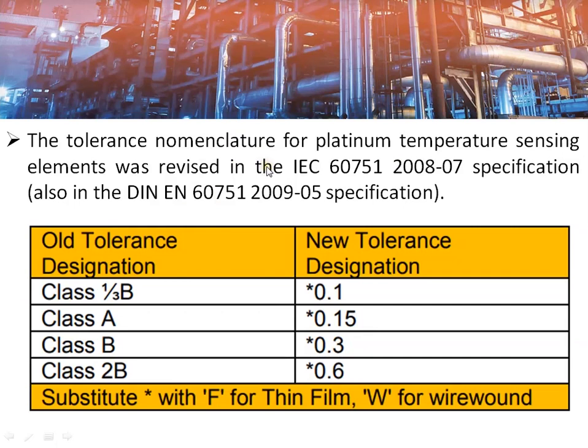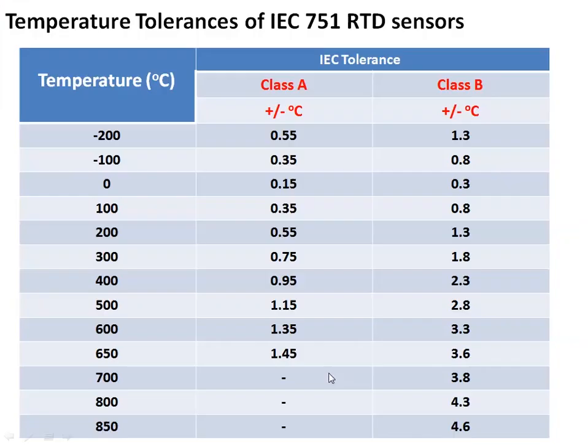The tolerance nomenclature for RTD temperature sensing elements was revised in later versions, that is IEC 60751-2008 and later. The old tolerance class 1/3 B was replaced by a new designation where the asterisk indicates either F or W — F stands for thin film and W stands for wire wound type RTD. For thin film type RTD, the new designation for Class 1/3 B is F0.1, for Class A it is F0.15, for Class B it is F0.3, and for Class 2B it is F0.6.